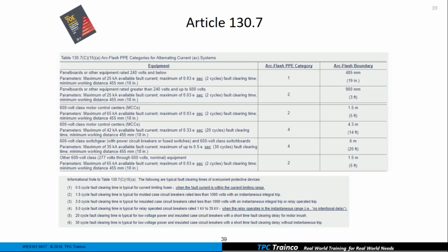But the clearing time was another issue. So what have they done? They put some informational notes to this table and told us that for current limiting fuses, those are going to have a typical clearing time of a half a cycle. For molded case breakers, less than 1,000 volts with an instantaneous integral trip, 1.5 cycles.